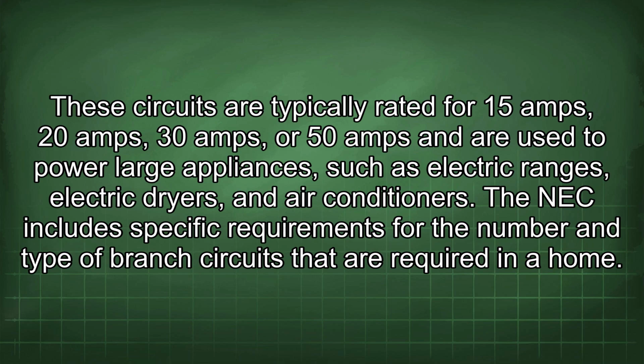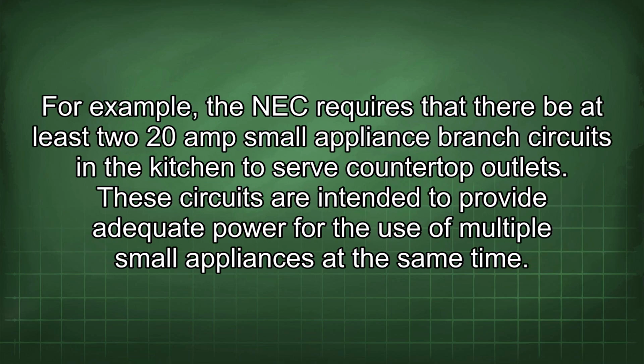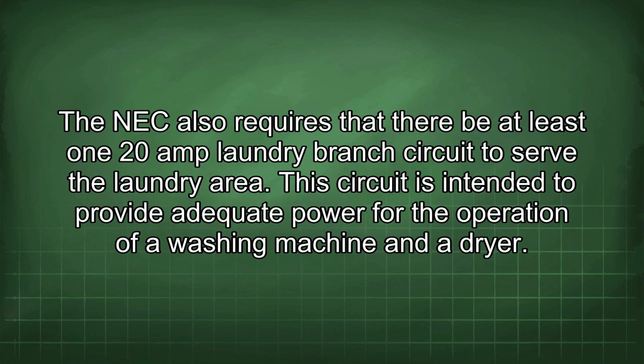The NEC includes specific requirements for the number and type of branch circuits that are required in a home. For example, the NEC requires that there be at least two 20-amp small appliance branch circuits in the kitchen to serve countertop outlets. These circuits are intended to provide adequate power for the use of multiple small appliances at the same time. The NEC also requires that there be at least one 20-amp laundry branch circuit to serve the laundry area. This circuit is intended to provide adequate power for the operation of a washing machine and a dryer.